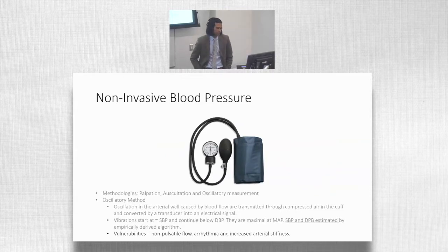Moving on to something else that everybody gets or should get, and that's a non-invasive blood pressure. Classically, this is either done with palpation or auscultation. However, we increasingly rely on the sort of oscillatory measures that we have available to us with these automated blood pressure cuffs.